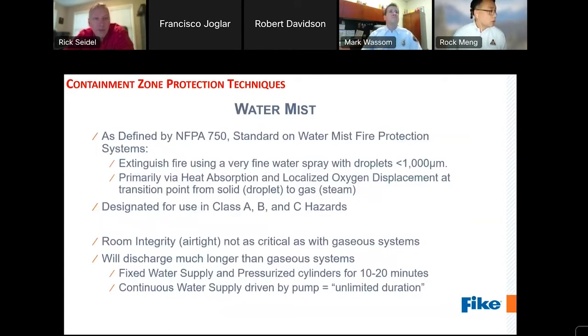Water mist is another option and a relatively recently evolving approach, and one that is proving to be very effective. Water mist is defined and guided by NFPA 750, Standard on Water Mist Protection Systems. It defines a water mist approach as anytime you're using very fine water spray droplets less than 1,000 micron to extinguish a fire. Water mist primarily works by absorbing heat and very localized oxygen displacement at the transition point where it turns from a liquid droplet to a gas in the form of steam.